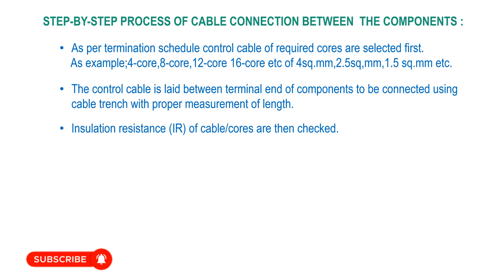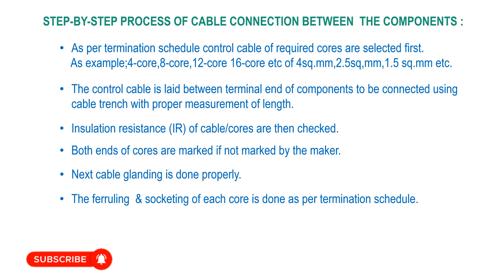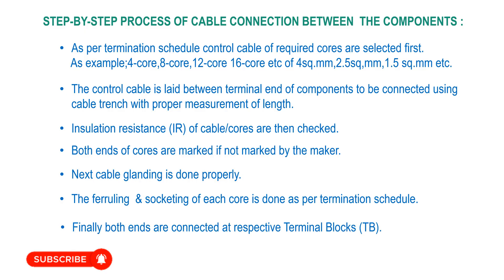The IR of the cable cores is then checked. Both ends of the cores are marked if not already marked by the manufacturer. Next, cable gland fitting is done properly. Then ferrulling and socketing of each core is done as per the termination schedule. Finally, both ends are connected at their respective terminal blocks.